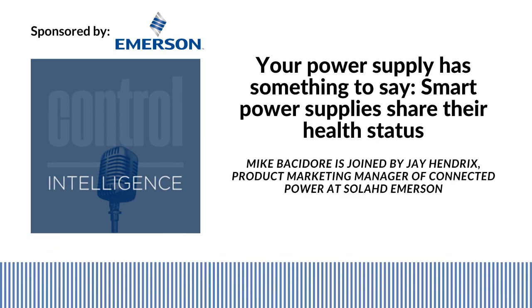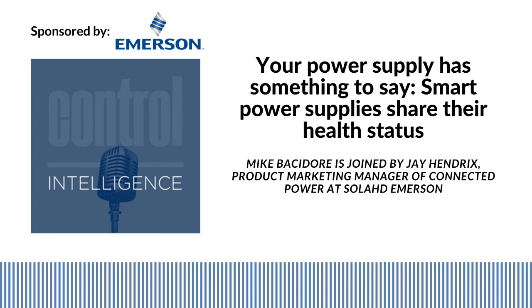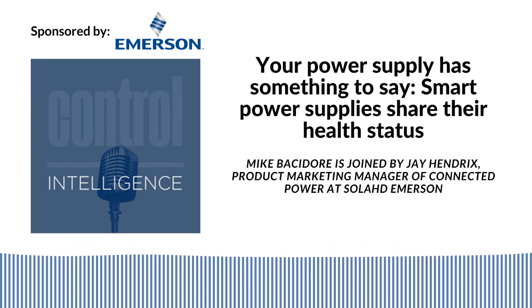But even better than hours, some manufacturers are building in useful life calculations. So this would be a calculation based on stress again. We talked about stress earlier, but stress in the power supply. So how hard it's been loaded and what's the environmental temperature that it's been operating in. And this calculation would give you a countdown indication.